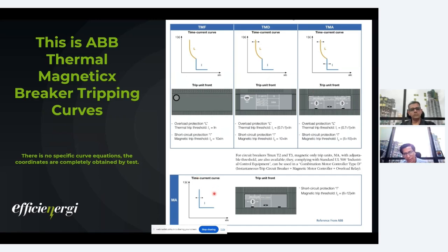Then there is a third one where we only need magnetic tripping, that is, we only need short circuit protection, and overload protection is taken care of by some overload relays. There we can use this kind of TCC curve. Again, these are single line curves. This will add up the tolerances, and we can see the maximum and minimum in this TCC.